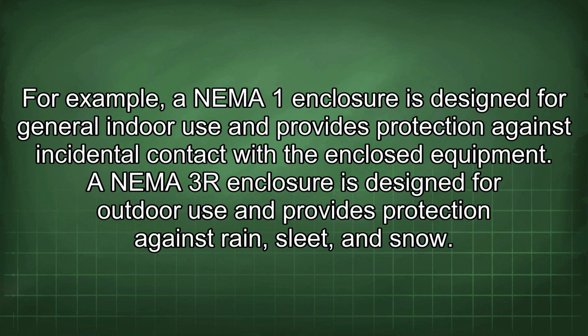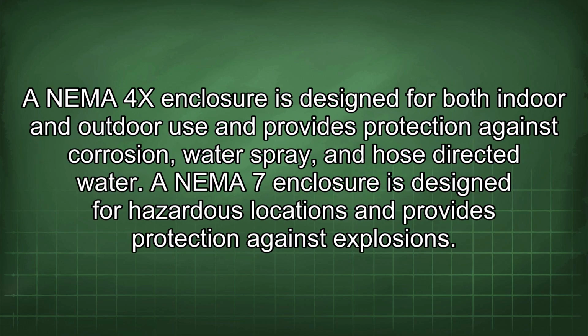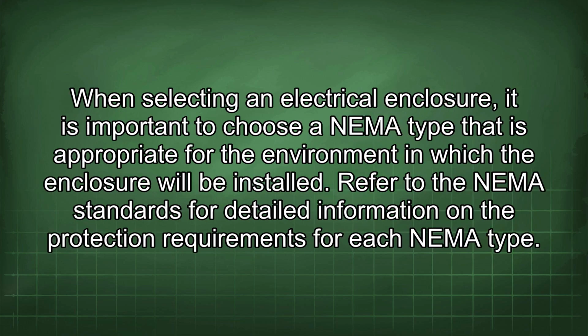For example, a NEMA 1 enclosure is designed for general indoor use and provides protection against incidental contact with the enclosed equipment. A NEMA 3R enclosure is designed for outdoor use and provides protection against rain, sleet, and snow. A NEMA 4X enclosure is designed for both indoor and outdoor use and provides protection against corrosion, water spray, and hose-directed water. A NEMA 7 enclosure is designed for hazardous locations and provides protection against explosions. When selecting an electrical enclosure, it is important to choose a NEMA type that is appropriate for the environment in which the enclosure will be installed. Refer to the NEMA standards for detailed information on the protection requirements for each NEMA type.